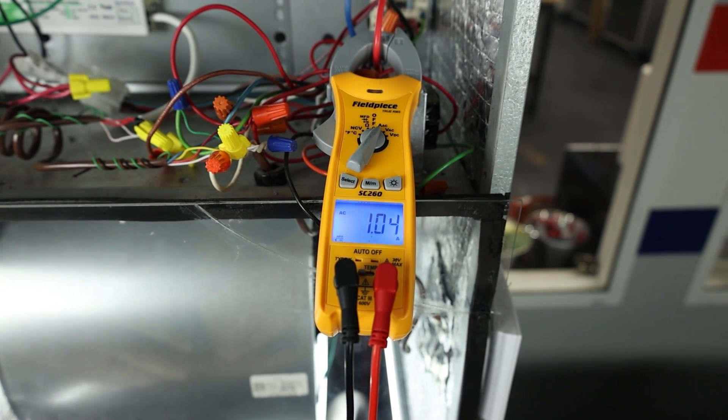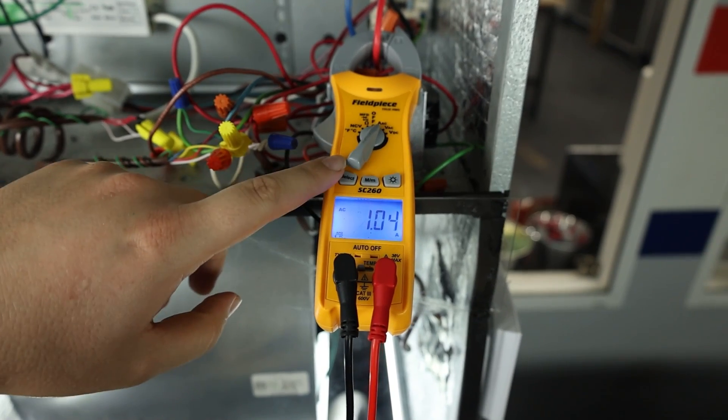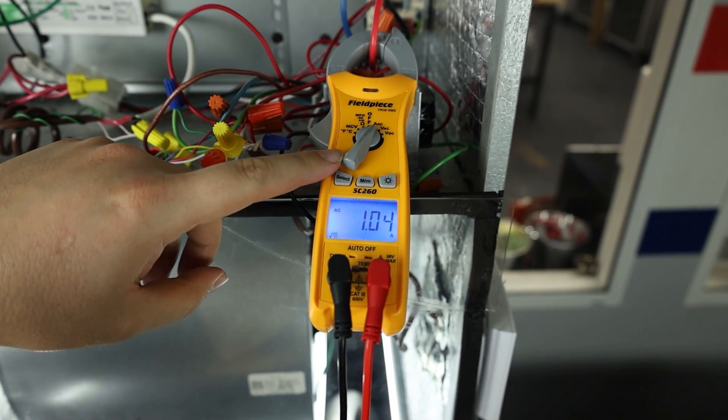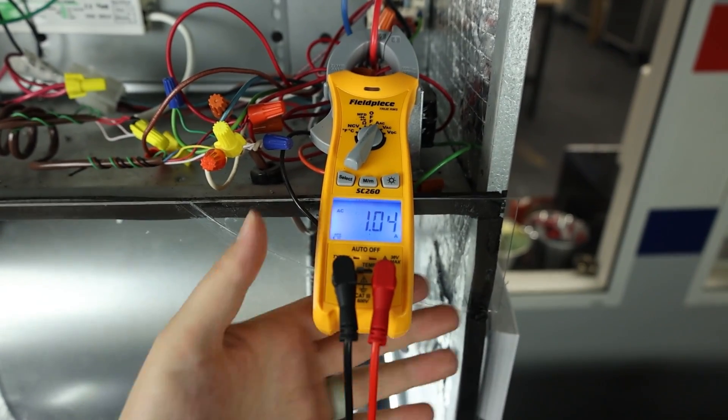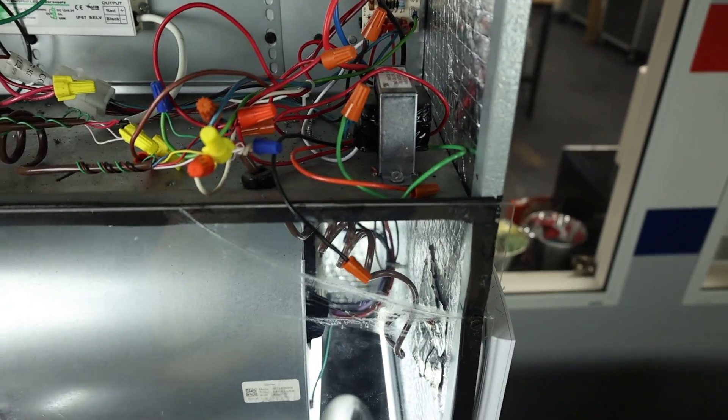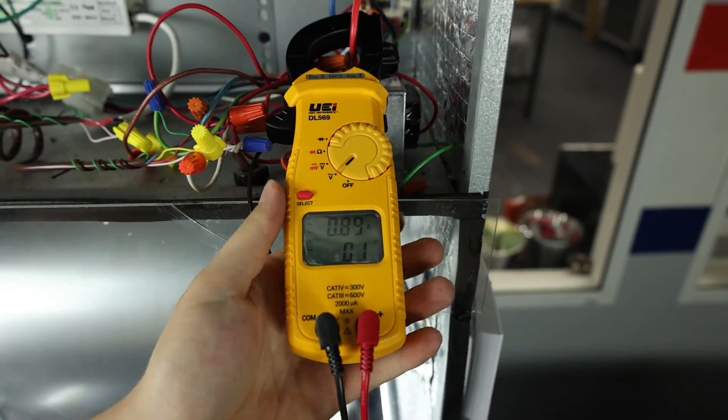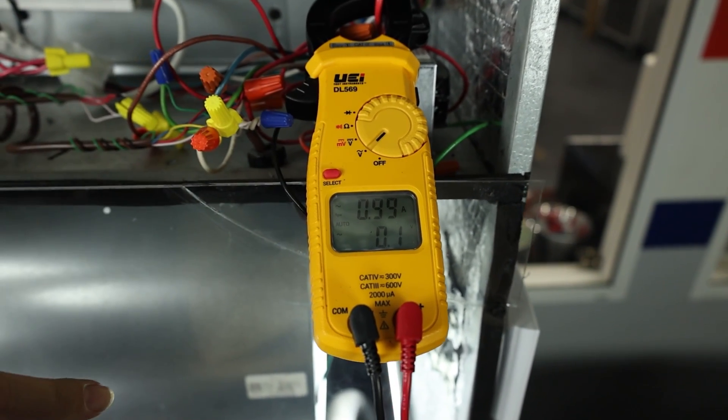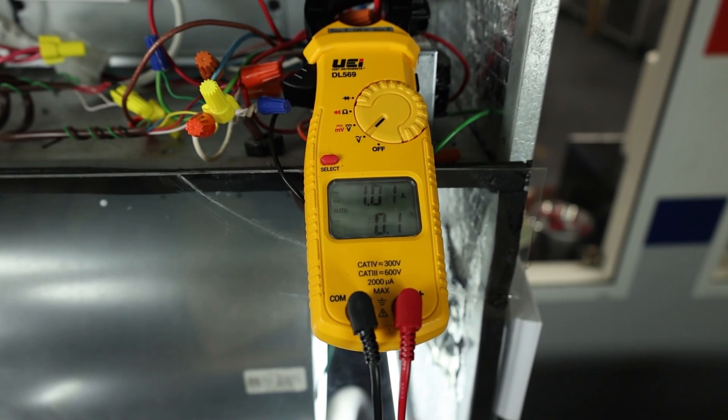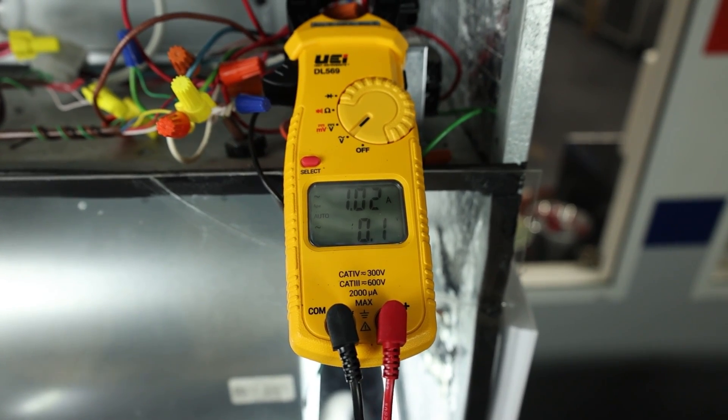We've come out here to our split system to measure amps on a blower motor. First, I've got the Fieldpiece set to AAC, which is the setting to measure amps. I'm measuring about 1.0 amps here with this meter. We can switch it out with the UEI one. As long as the UEI meter is set to any of the settings, it will measure amps at the top of the screen there. We're reading about 1.0 amps as well. That's how to measure amps with these two meters.